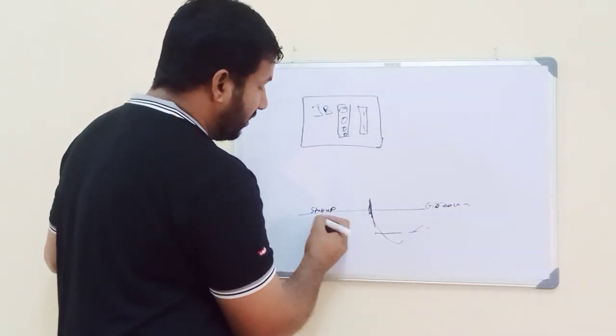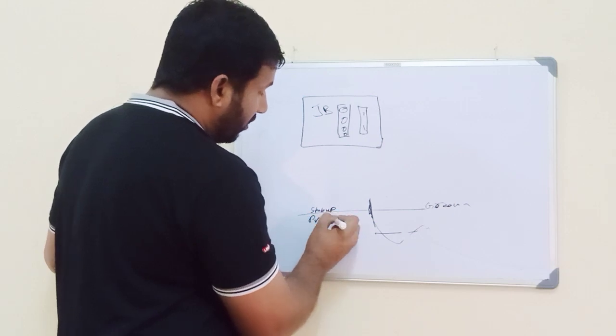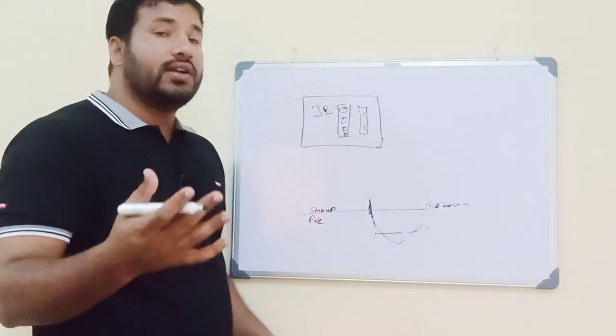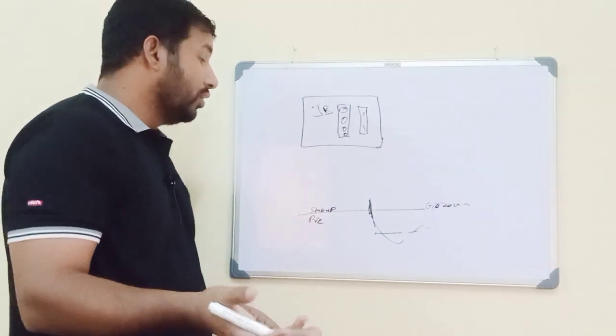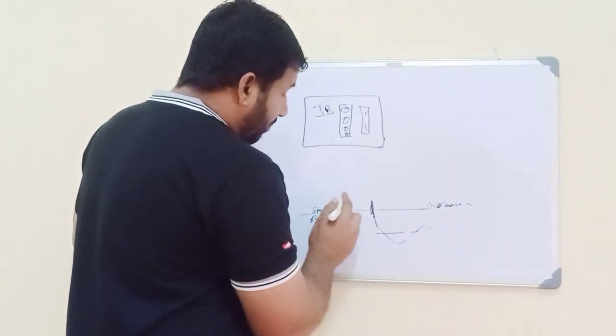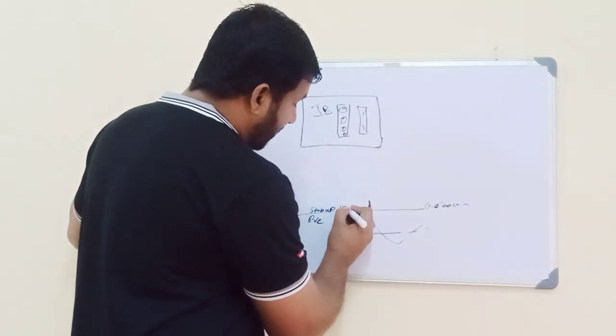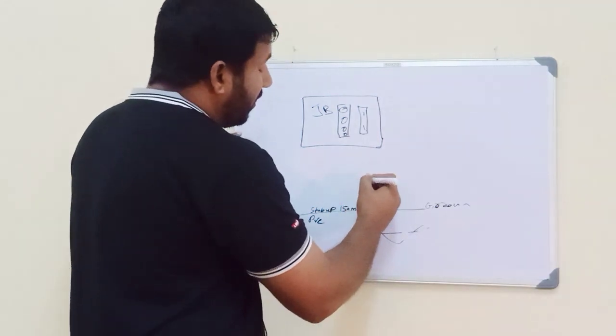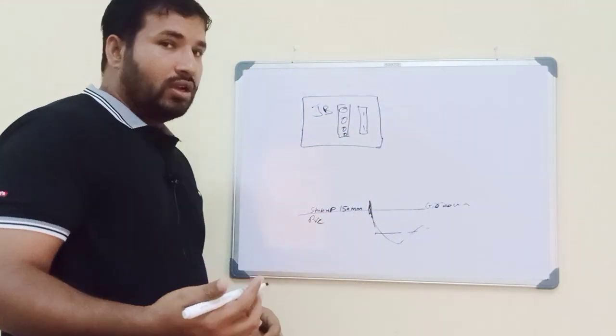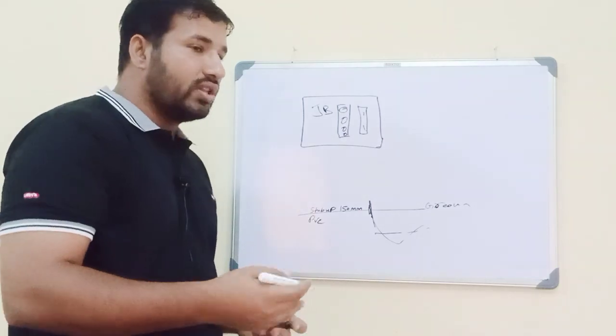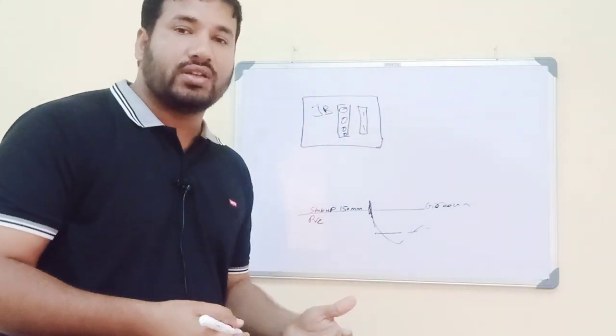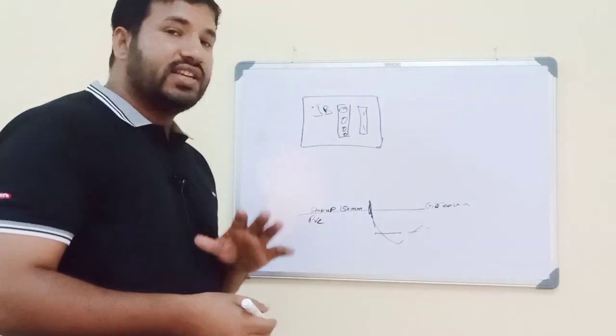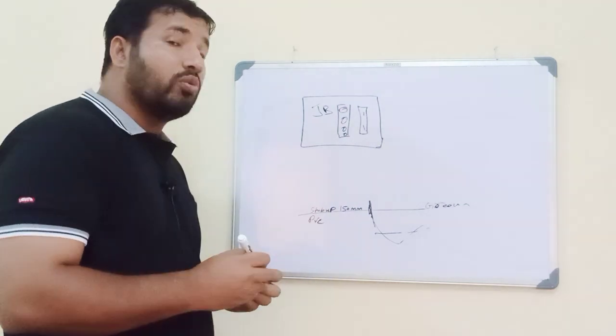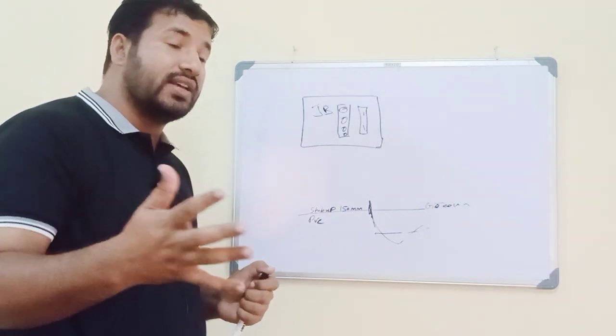Stub up is like PVC - what kind of PVC is already discussed in the conduit video. The stub up maximum we can use is 150 mm. If this is a hazardous environment and the JB distance is more than 1 meter or 1.8 meter, then we have to use RGS PVC coated conduit. You already saw that in one short video, in our area we use that one.